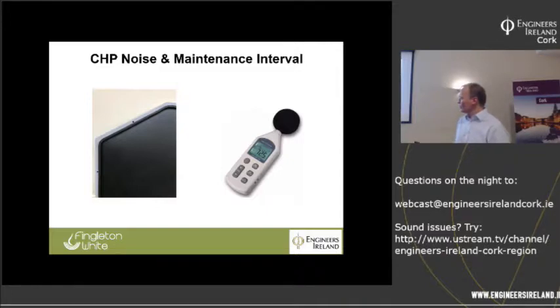Not going to be too comfortable either. We have overcome that problem, and the way we did it, on the left-hand side here, you can see the acoustic panel being taken off the side of our machine. We have a polyester sandwich with a vinyl backing attached to the steel panel, and that makes up the acoustic enclosure. Then we have vibration mounts on the machine itself and on the engine mounts. That combination brings down the noise substantially.